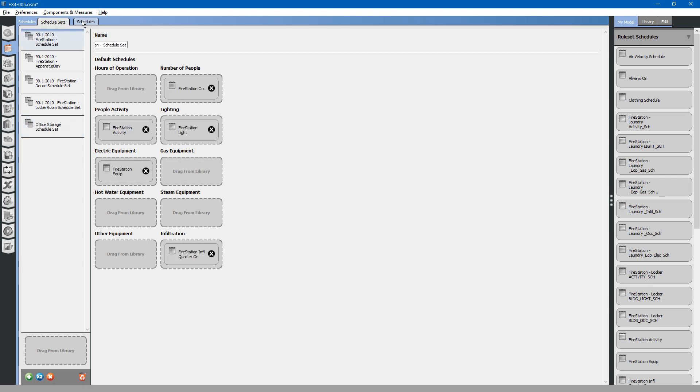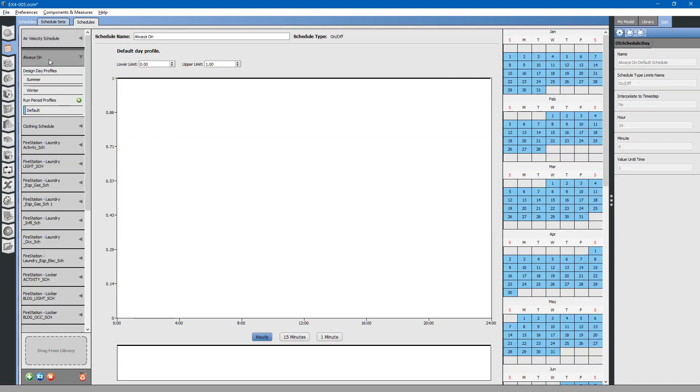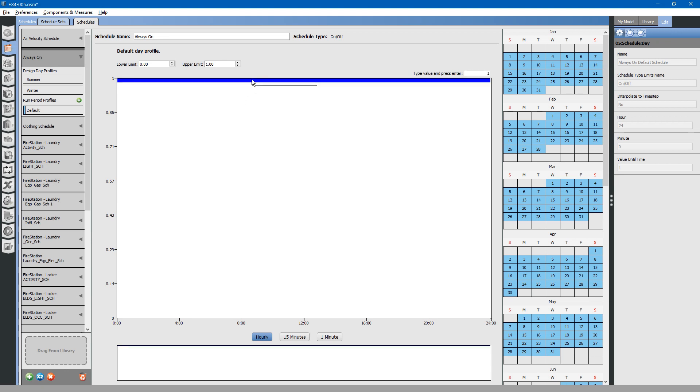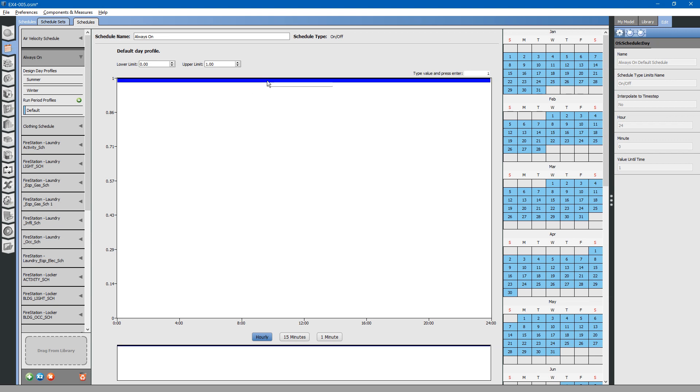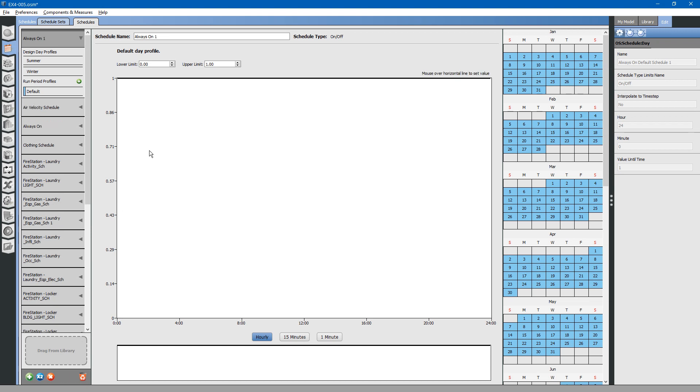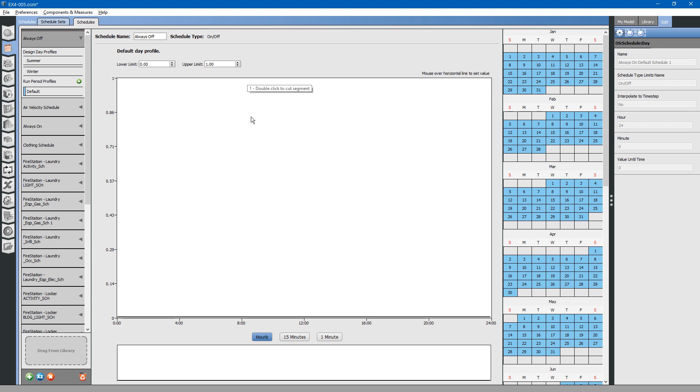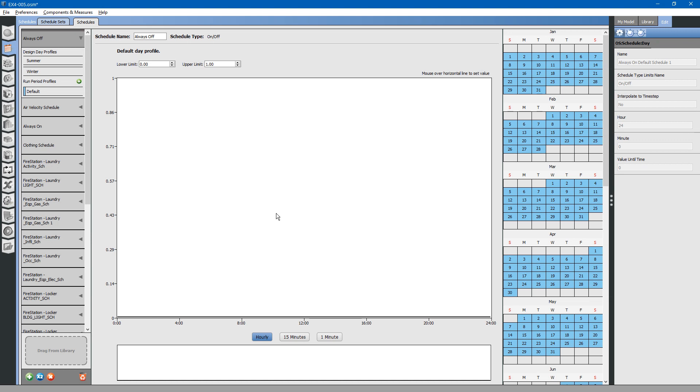Next, we will go to the schedules tab. These are the individual schedules. Let us look at this one, Always on. This is a common type of schedule used for energy modeling to override equipment to ensure that the equipment is in the on position throughout the entire year. The default schedule for this is 1. Likewise, we can create a new schedule just by copying the plus 2 on here. We will call this always off. To change the value to zero, hover over the line and type in zero. Enter. Now, this is always off.